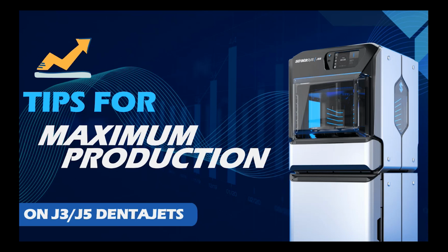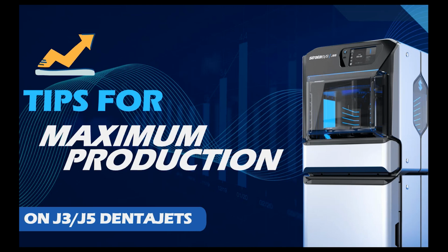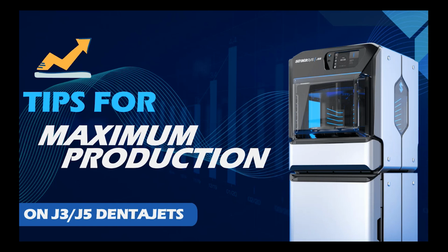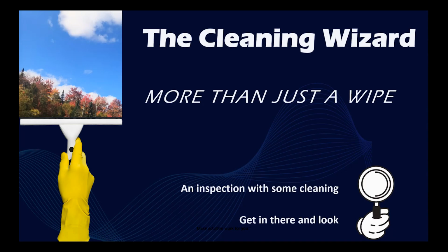Thank you. Good morning. Again, my name is Adam DeSanza, Technical Account Specialist for Medical and Dental J3 and J5s at Stratasys. I'm here to give you the absolute top level tips to get maximum production from your DentaJet. The number one tip is the cleaning wizard.